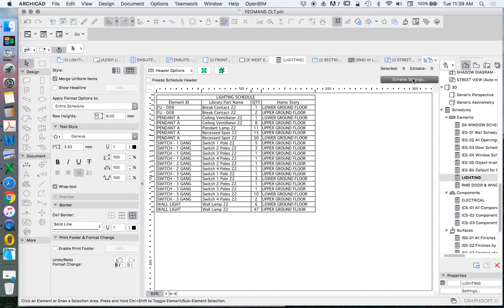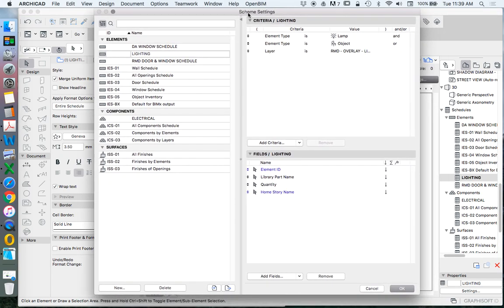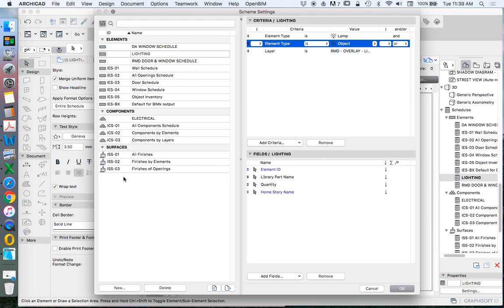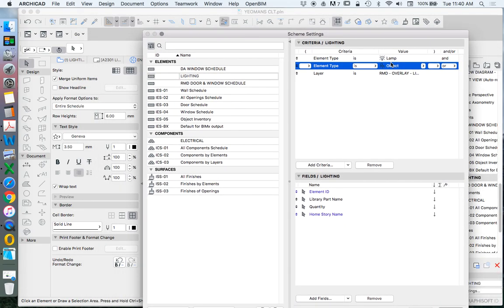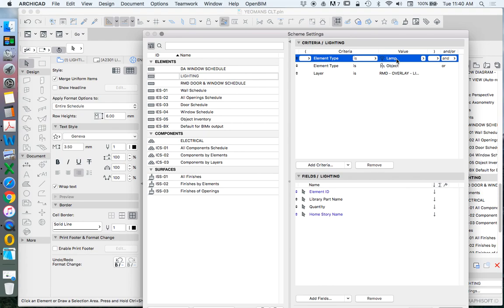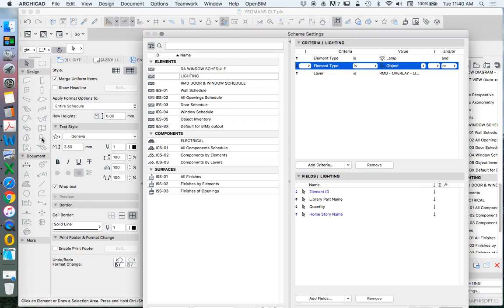When we go to scheme settings, we break things up into criteria and fields. Criteria is what elements are going to show — what is being scheduled. In this case, we're scheduling lamps and objects. We need both because in ArchiCAD, lamps are the lamp tool under 'More' and objects are the object tool. For our lighting schedule we want both, and we also want to filter by layer so only objects on our overlay lighting layer are visible.